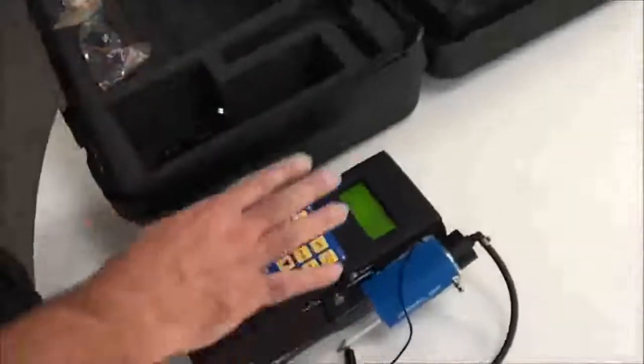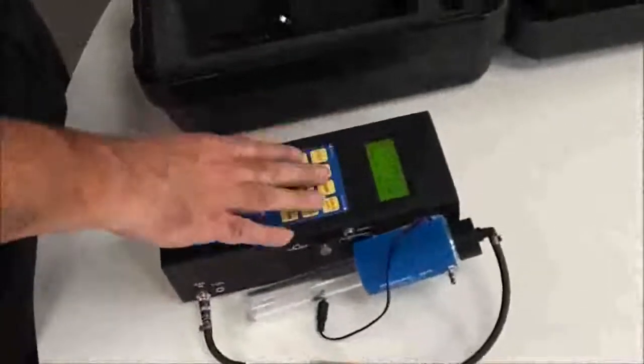Now we'll hook up the entire system. My recommendation is, before you start testing, charge the unit overnight. Give it a full charge. Make sure that you're on a powered outlet, and that when you leave, the unit is charging. There's a switch inside. If you turn the unit on and plug in the charger and you don't see an increase in the power of the unit, then the switch inside is probably in the off position. That's for non-rechargeable batteries, so that you cannot accidentally overcharge alkaline batteries. You may have to open the small cover on the back and flip that switch up.